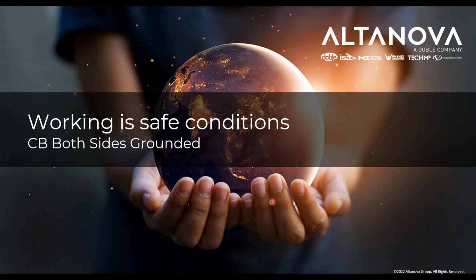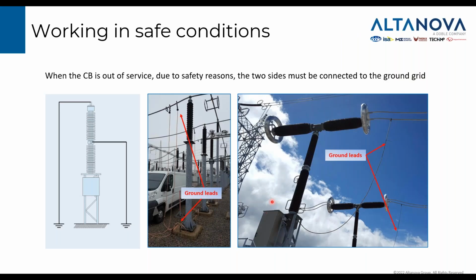We don't have to forget that the circuit breakers are in substations and maybe very close to live bus bars. It is important to perform all the tests in safe conditions. When the circuit breaker is out of service, for sure, the two sides of the circuit breaker are connected to the ground, because whatever is floating in a substation can easily reach very, very high voltage, dangerous for the operators. So this is the condition that you would like not to change.